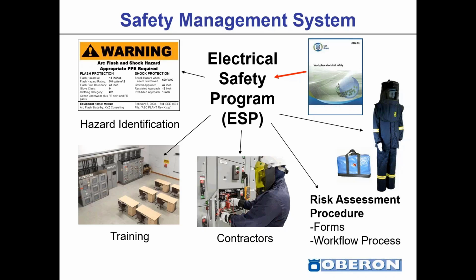For example, if your program were following, say, ANSI, some type of an occupational health and safety management system standard and its framework, it would have hazard identification, training, roles, responsibilities, and your risk assessment procedures such as forms, workflow process, and the standards. You see there's one arrow pointing towards the program, and that would be your NFPA 70E or CSA standard that's being used as information. So more or less a toolbox that would be used in order to build up your program, and then your program defines everything that surrounds it, including your electrical specific PPE, tools and equipment, or arc flash PPE for this presentation's purpose.